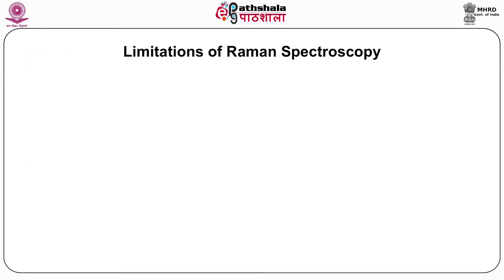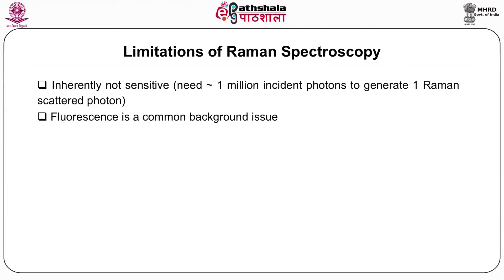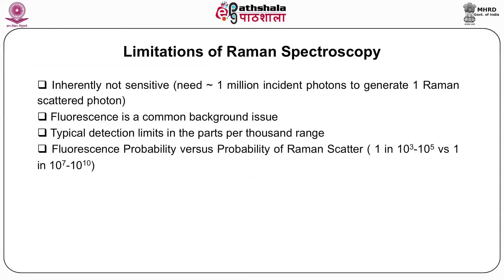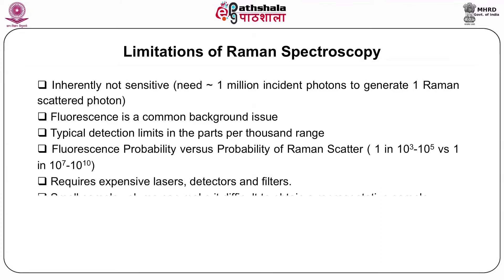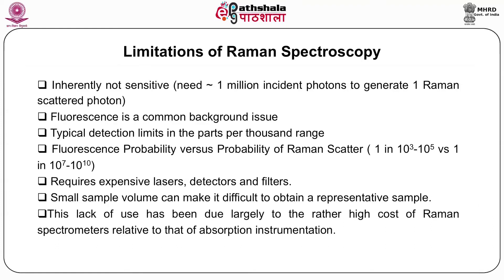Limitations of Raman spectroscopy: it is inherently non-sensitive, needing around 1 million incident photons to generate one Raman-scattered photon. Fluorescence is a common background issue, with typical detection limits in the parts per thousand. Fluorescence Probability versus Probability of Raman Scatter is 1 in 10^3 to 10^5 versus 1 in 10^7 to 10^10. It requires expensive laser detectors and filters. A small sample volume can make it difficult to obtain a representative sample, and the high cost of Raman spectrometers relative to absorption instrumentation has limited its widespread use.